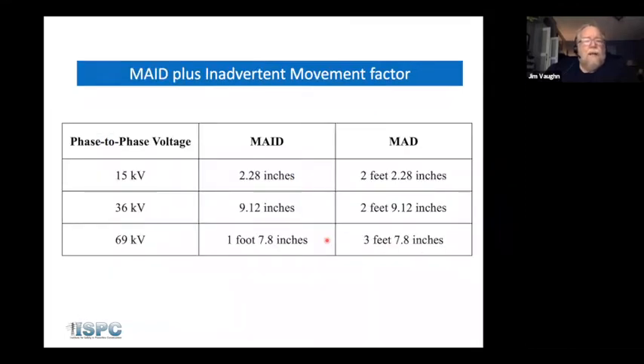So you see here then in this table that we created for the presentation, at 15 kV, the MAID is 2.28 inches. The inadvertent movement is 2 feet, and that's where you get the 24 inches, 25, 26, 27 inches. We go up to the next size. At 36 kV, the MAID is 9.5 inches, so 2 feet 9 or 2 feet 10 inches. At 69 kV, the MAID is 1 foot 7. Something's wrong about that. I have to go back to that later. 1 foot 8 inches, or it may be 7 inches, 0.8.